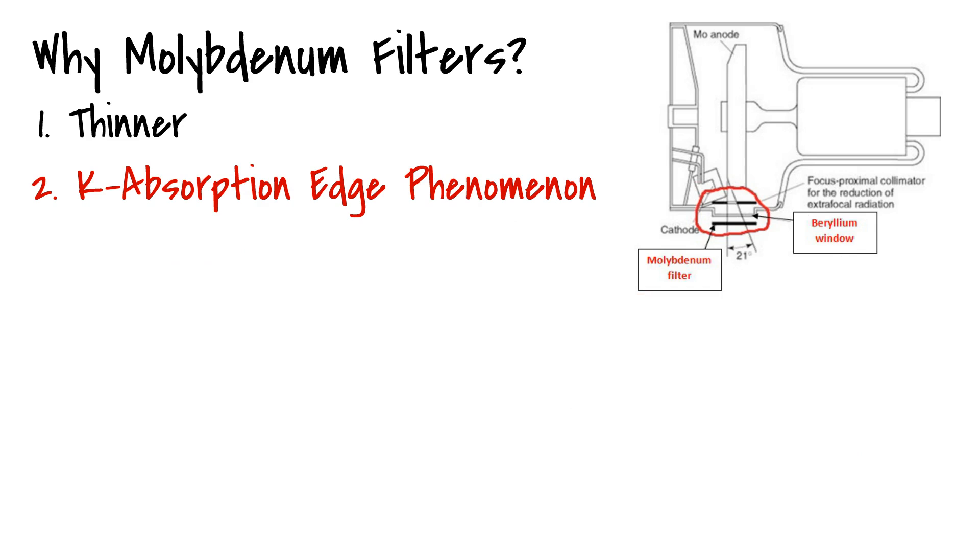This is known as the K-absorption edge phenomenon. Simply put, it means that molybdenum filters are able to selectively allow photons to pass through if they have energy that is only slightly below the binding energy of molybdenum.